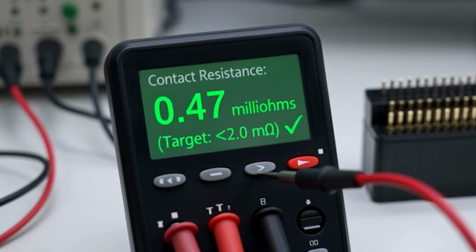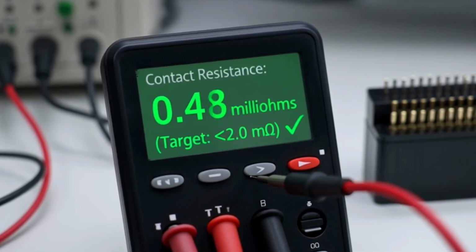The connector's contact resistance is measured with a 4-point micro-ohmmeter. Each contact point individually shows resistance below 0.5.